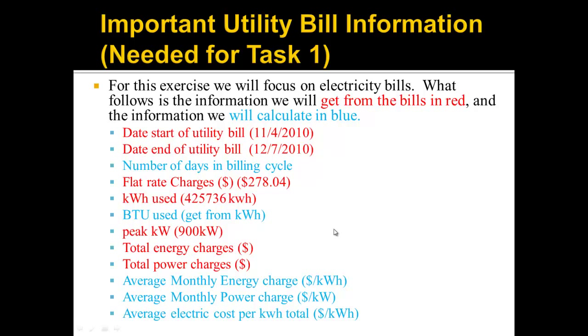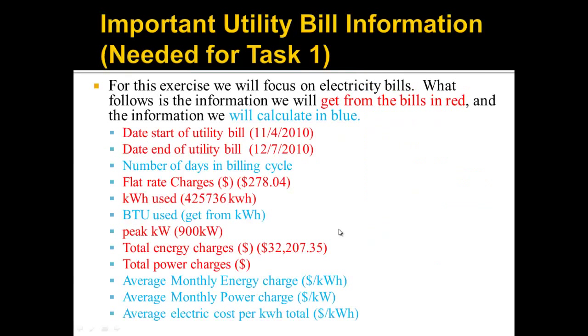Now let's look for the total energy charges. The total energy charges are charges for kilowatt hours. Remember, kilowatt hours are energy and kilowatts are power. We want to find everywhere there's a calculation on the bill involving kilowatt hours. We can see there are two up here and one down here. The bill might also just say 'energy charges.' We have to add all those up and we get a total of about $32,200. We'll update the table.